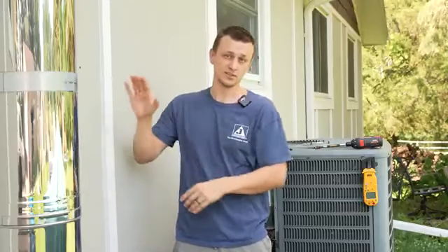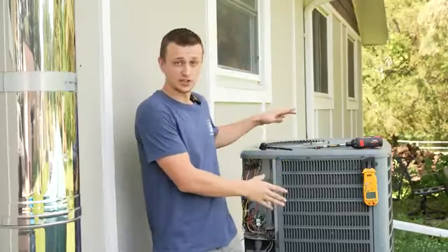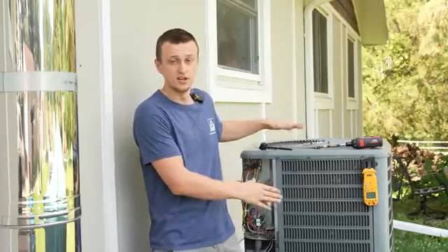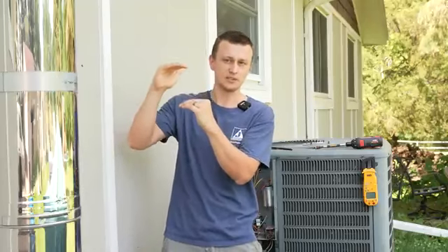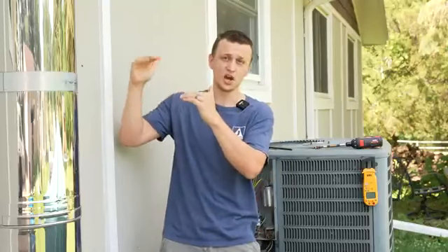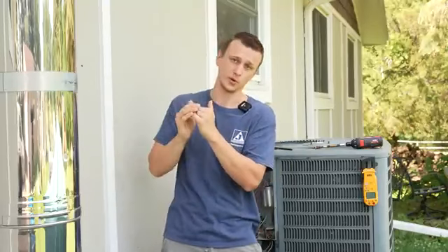And the most common symptoms of a unit being low on refrigerant is when everything is running, the fan inside is running, everything outside is running, the fan and the compressor, yet the house is not cooling off. Or maybe it is cooling off, but it just never reaches the set point. If you have your thermostat set to, let's say, 75, it never gets there. It just hovers around 78 and it struggles to go down.